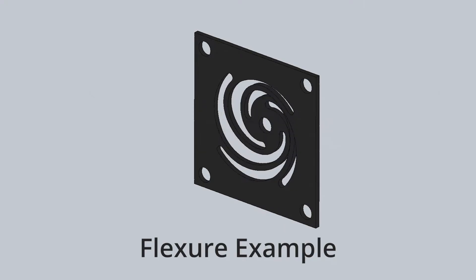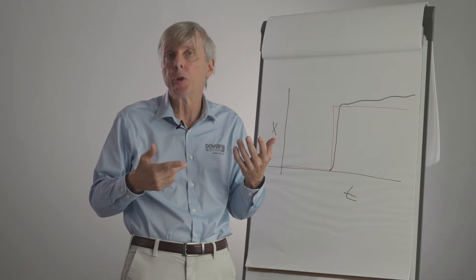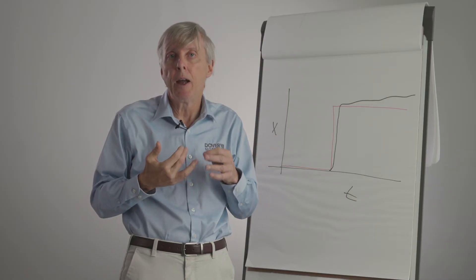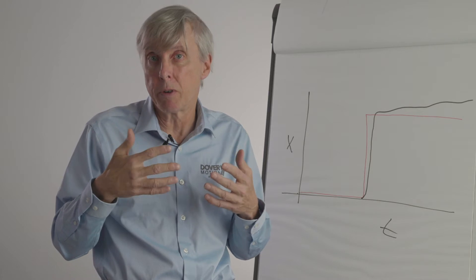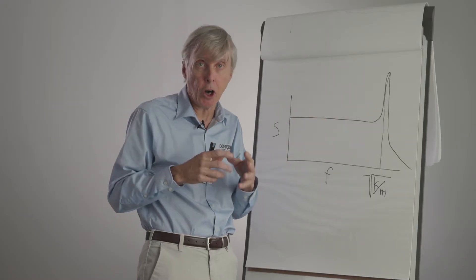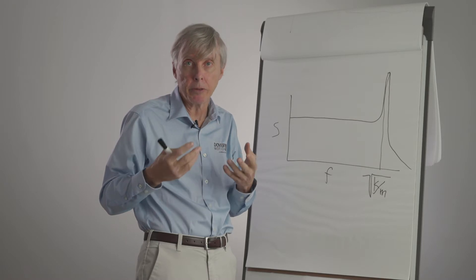In addition, the nature of the leverage is generally a flexure lever. These are prone not only to low stiffness in the direction of motion, but out of plane weakness, which poses a real problem because instruments have vibration sources, they have fans, they have pumps, and we have routinely seen our customers struggle when the flexural guideways and lever amplification leads to a reduction in the stiffness, susceptibility to out of plane motions, and lower first fundamental resonance. They are relatively costly products and require some fairly sophisticated electronics.